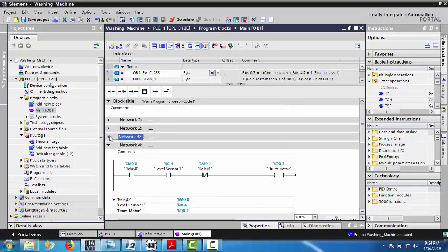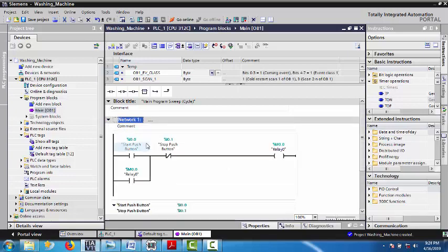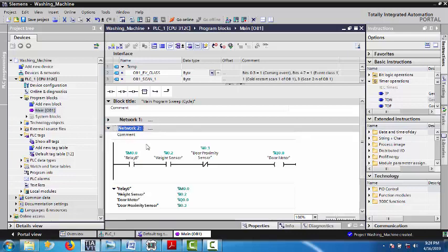I hope you understood how it is working exactly. I will just repeat it quickly. First is the common latching circuit. It will never change. As soon as the circuit starts and if the weight is greater than 20 kg, the door motor is going to start. The door motor will slowly close the door. When the door is closed, the door proximity sensor will be sensed. As soon as it is sensed, there is no need for the door motor to operate, so the door motor will stop operating.